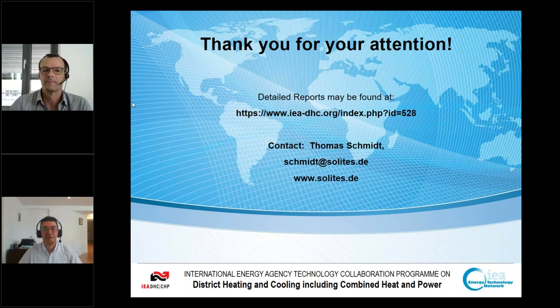Thank you, Thomas. May I add something? Sure, go ahead. Also, if the solar irradiation is plus or minus 15% from normal, what happens if there's a lot of solar is that the return temperature will go up. It means that the temperature into the solar system will be higher and the production will be lower. So it will regulate itself a bit. So normally we hit quite well.